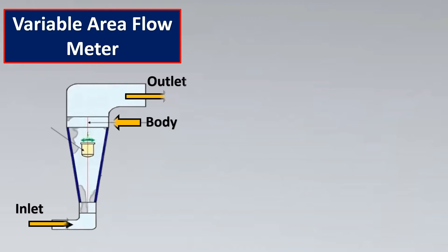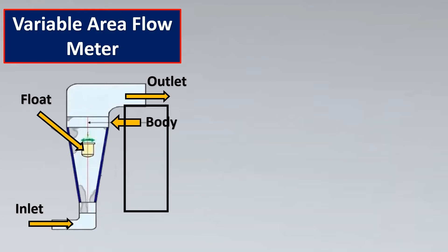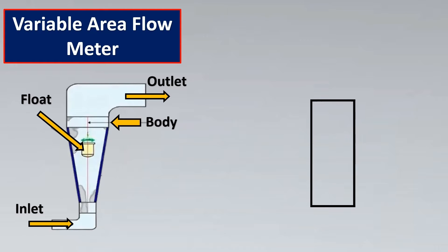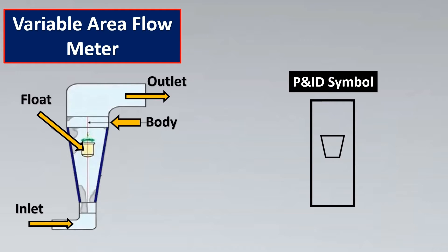Variable area flow meters have an inlet, outlet, body, and most importantly, a float. The P&ID symbol follows the same logic — first the body is drawn, then the float in between. This is the P&ID symbol as per ISA 5.1 for variable area flow meters.